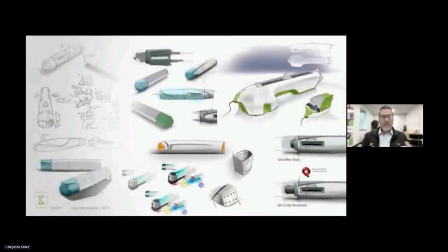So, in your design controls, you move further down the development process. Now you get into phase one of your design controls, and you start coming up with concepts. Okay. So our human factors engineering process is jiving with our design controls. We get into phase one here, into this ideation phase, and we develop some concepts. So we start with simple concepts, drawings, sketches, 2D schematics, layouts. We show them to users. We talk to users. We have interviews. We get some feedback. We're doing this kind of simple stuff.